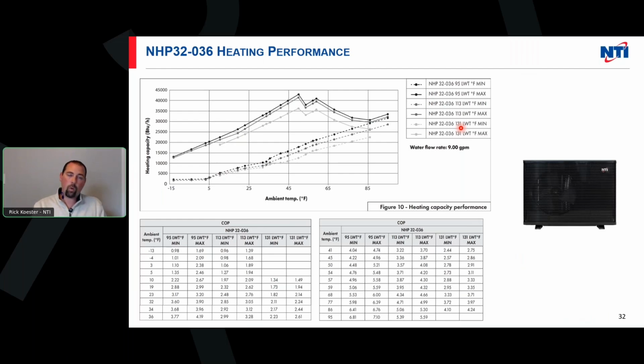So being inverter, it can ramp up in that entire range. If I'm looking at a 5-degree outdoor day, I can come up here and see what temperatures I can maintain. And I have another chart you're going to see that's in our manuals. If we're designing around a specific water temp, you can see the extended range and whether we're able to get those consistent water temps, which is really nice. So max performance, lower performance on the dashed.